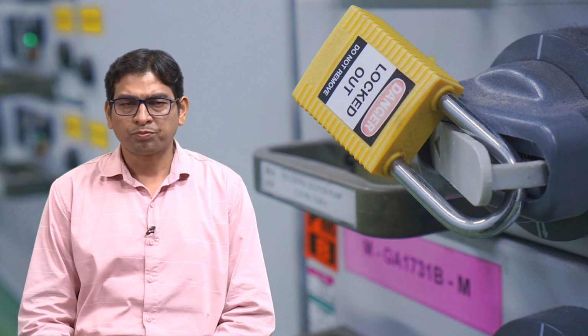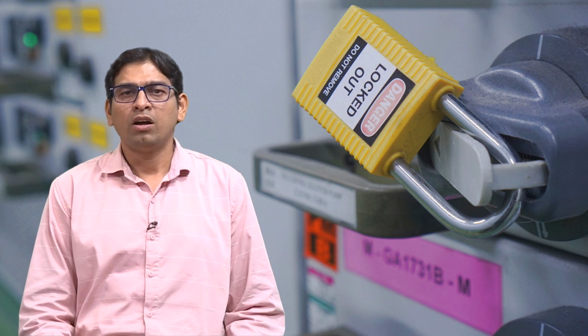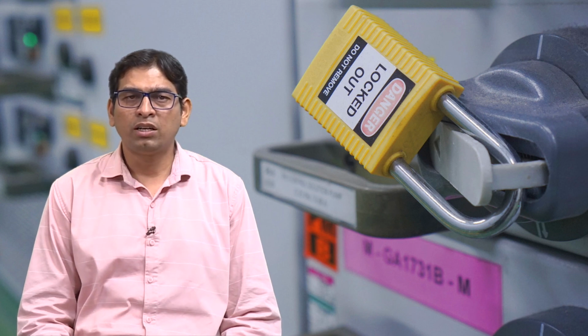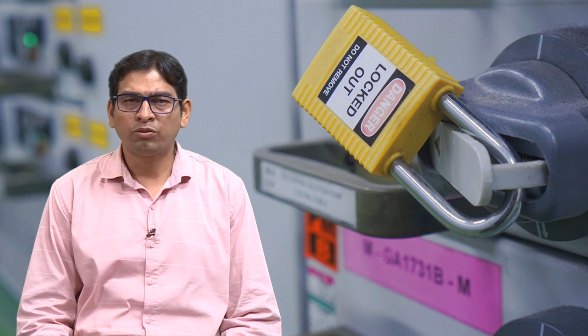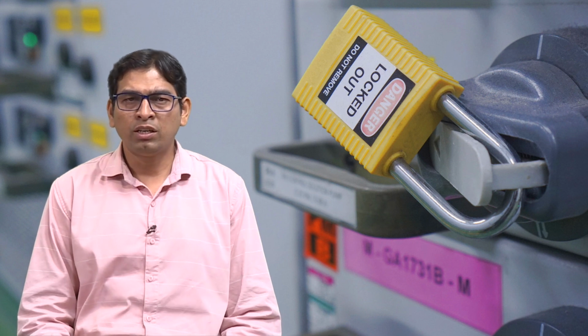First, personnel from the new incoming shift must install their lockout tagout devices. Then the locks and tags that were installed by the departing work shift should be removed.